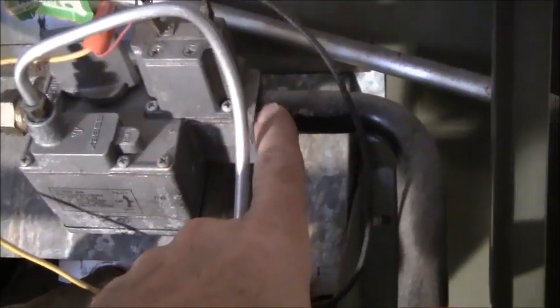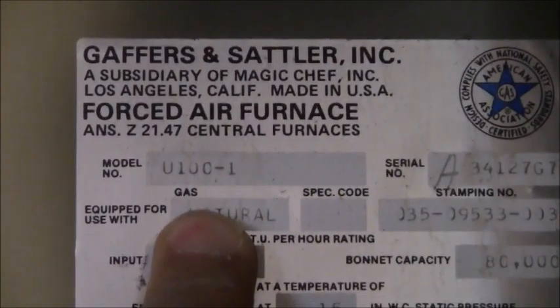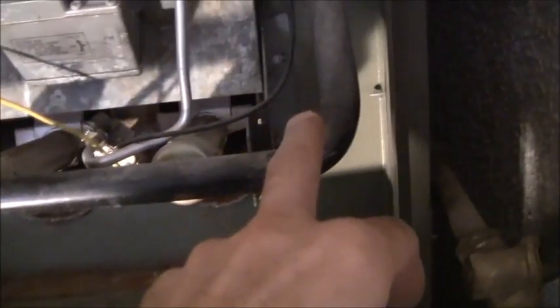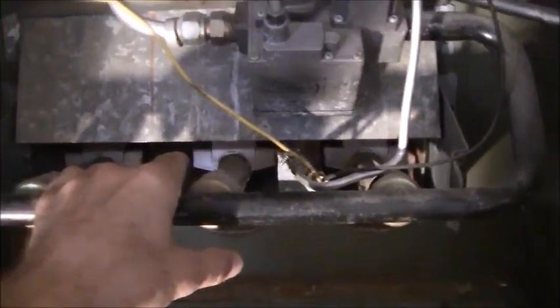This unit is so old that I don't even have a tap on the valve to determine what the manifold pressure is, number 1. Number 2, my data nameplate doesn't even tell me what the correct manifold pressure should be anyways. And this thing is so old that I can't even go to the manufacturer, put in the model number, get the spec on this, and determine what the correct orifice size should be or what the correct manifold pressure should be. Because back then, they didn't even have the internet 40 years ago. So, you know, I'm just dealing with ancient technology.